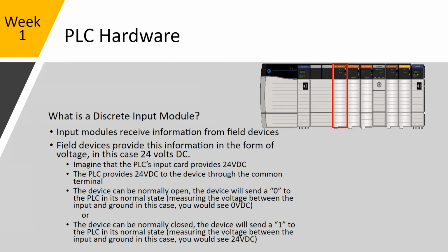So digital inputs are discrete. They are either on or off. So in this example here, this would be a 24 volt input card. You can have 120 volt input cards as well, but you're essentially closing a circuit. So digital inputs are going to be monitoring if a pump is on, if a door is closed, if a switch is closed. Does that make sense?